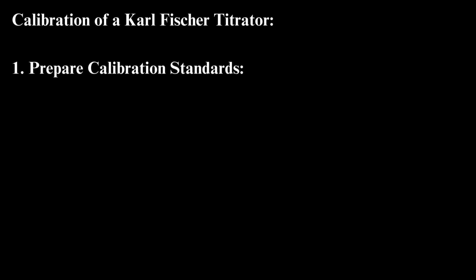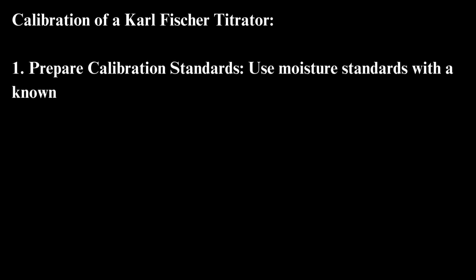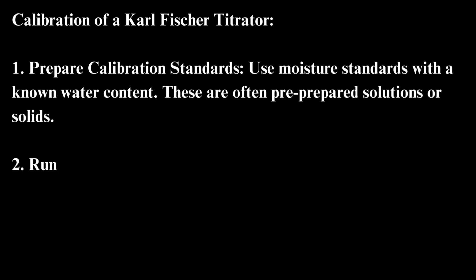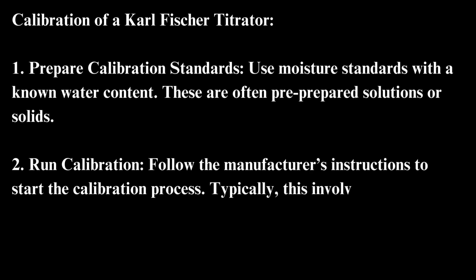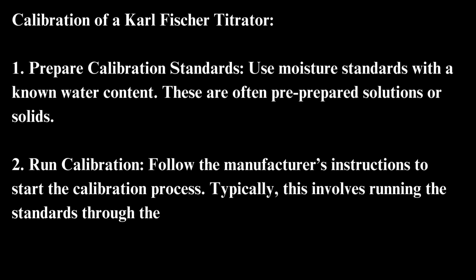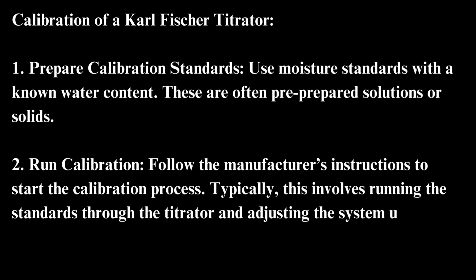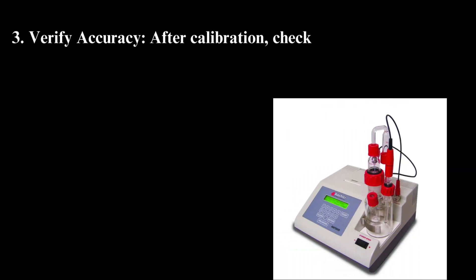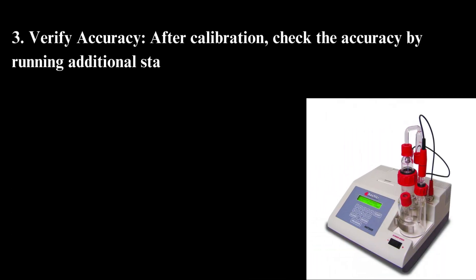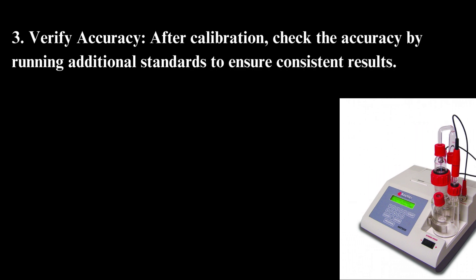Calibration of a Karl Fischer titrator: first, prepare calibration standards — use moisture standards with a known water content, often pre-prepared solutions or solids. Then run calibration by following the manufacturer's instructions. Typically this involves running the standards through the titrator and adjusting the system until the readings match the known values. Finally, verify accuracy by running additional standards to ensure consistent results.